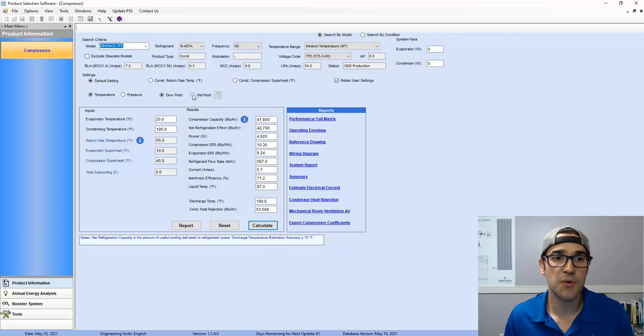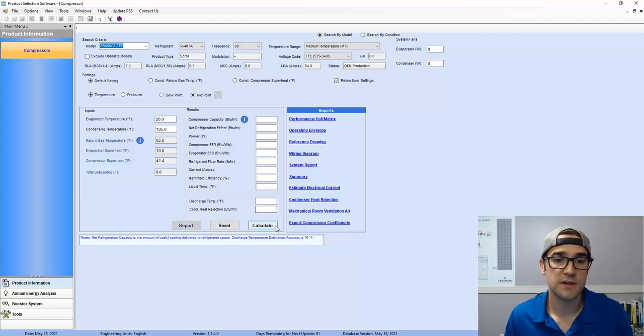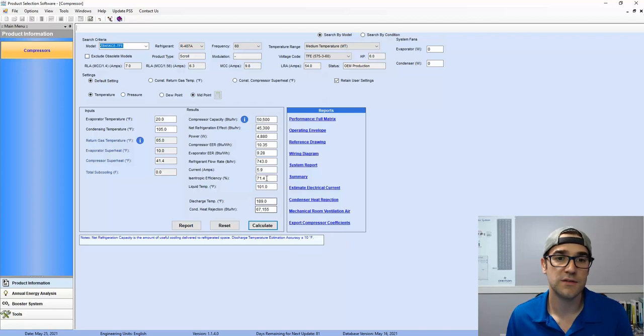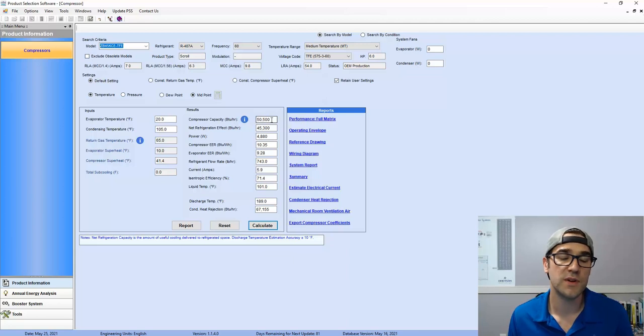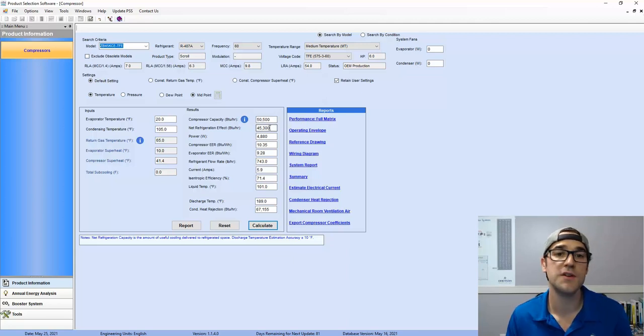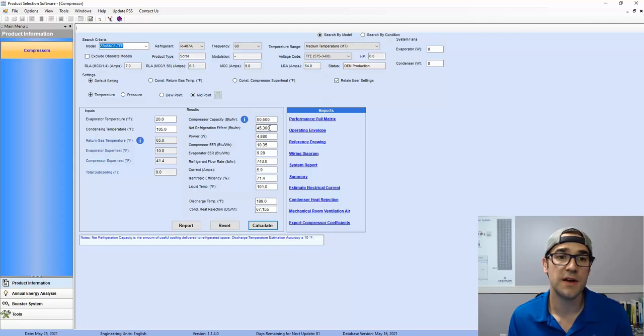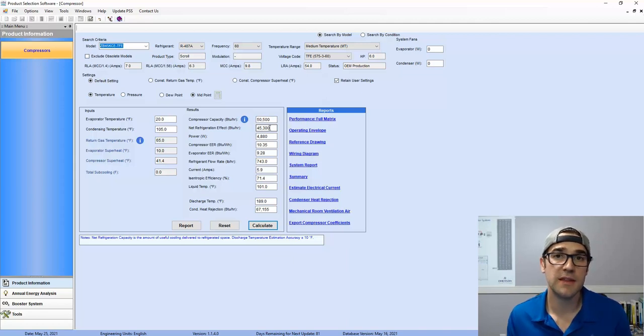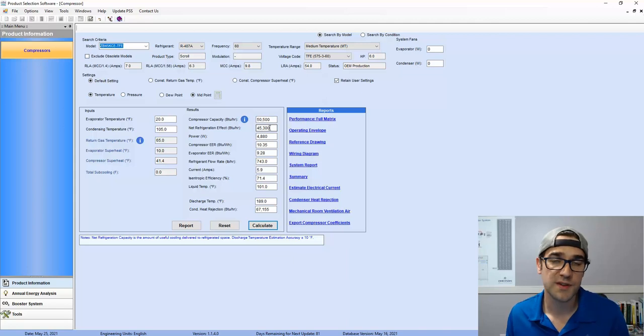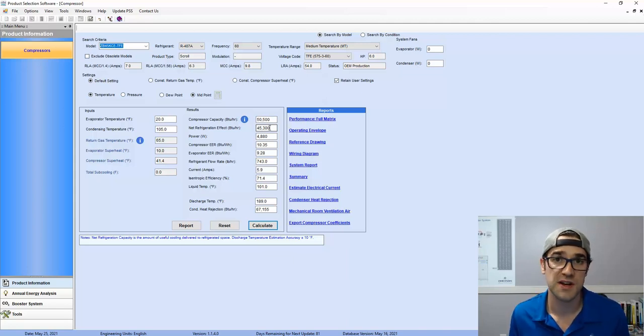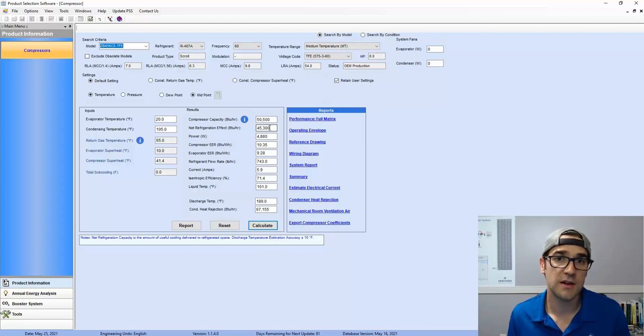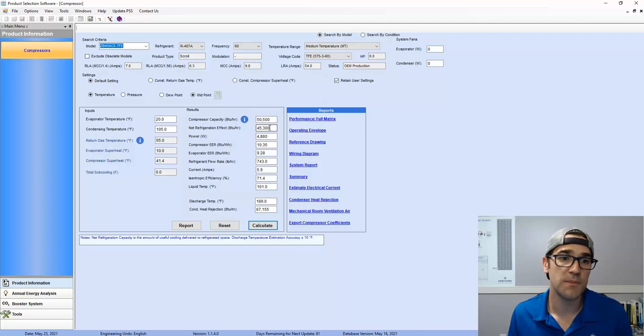If I did it by the midpoint now, because this is a glide refrigerant, calculate, now we're even higher. So instead of 47, we're at 50,000. So we're looking at 25, 26% oversize in the compressor. And now we're at 13% oversize on the evaporator. And the issue with this is now you don't want to be too oversize because you could have short cycling issue. Most systems are oversize. But if they're designed correctly, you can a lot of times have smaller equipment.